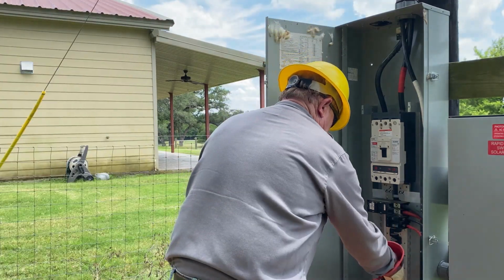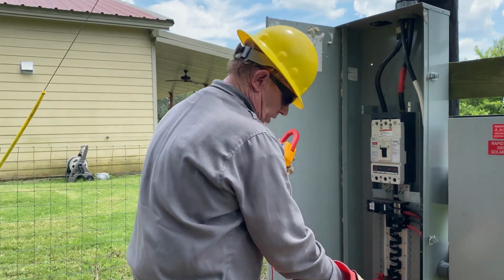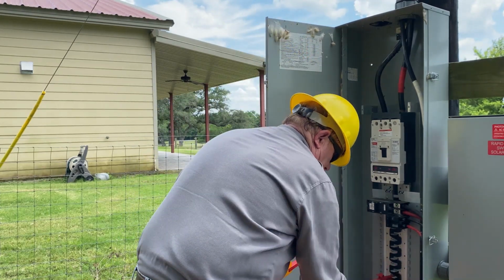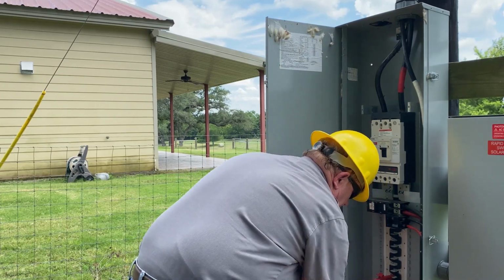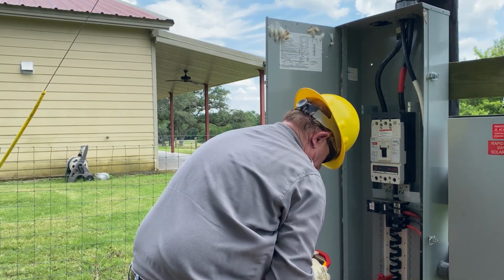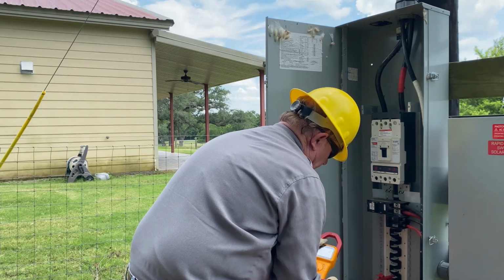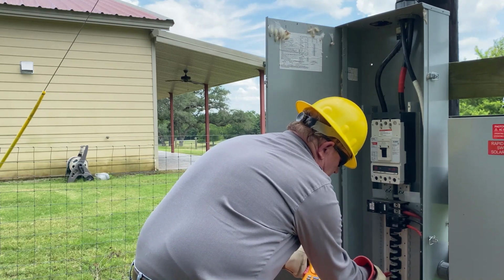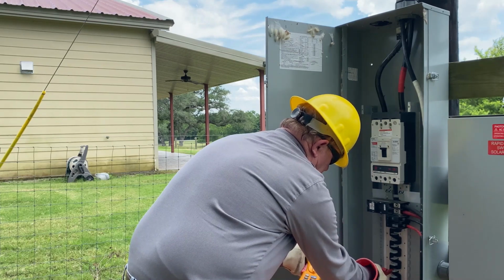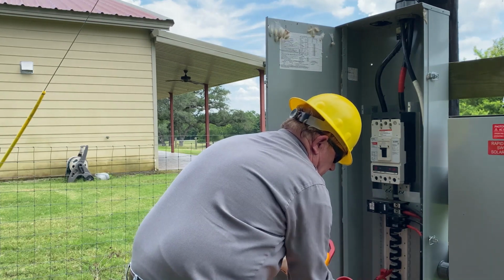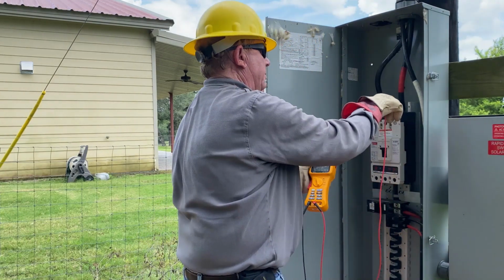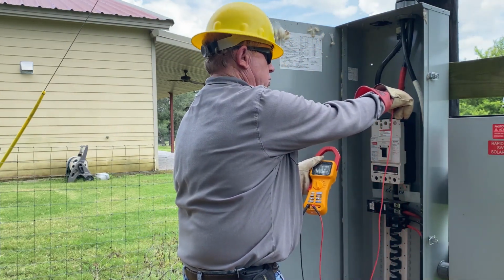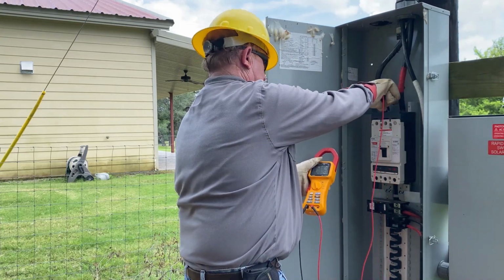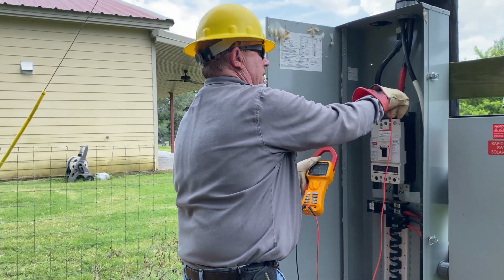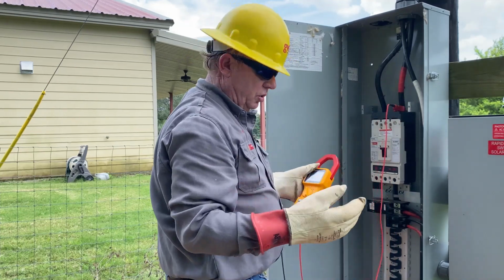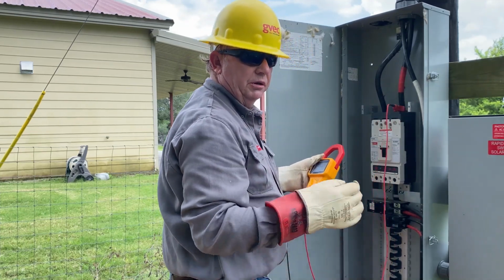If I take my hot lead, we're at 240 volts. I'm going to clip on down here, and I'm going to see 119.6, 126.0. We'll come up here and check it on top of the breaker. 126.0 and 119. Now, the position of the neutral clip on the voltmeter is the most important.